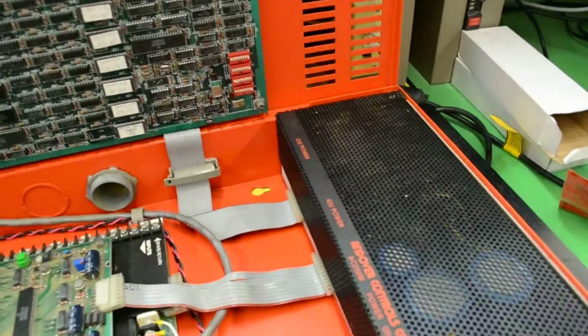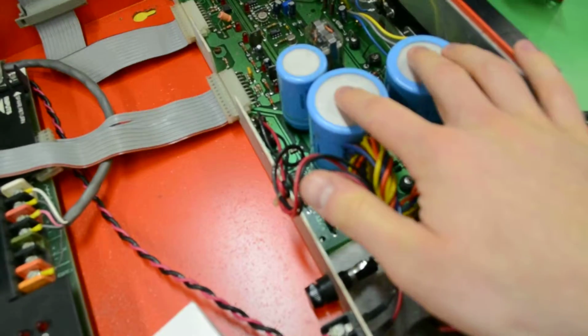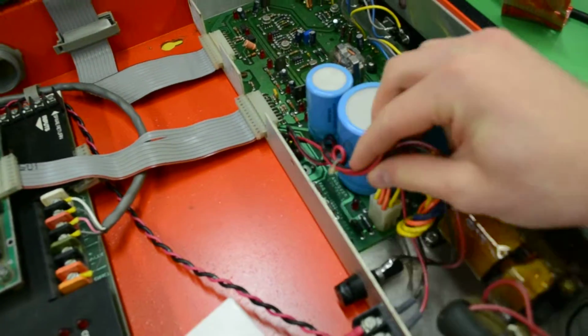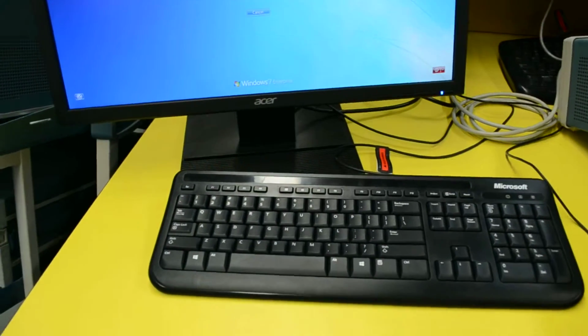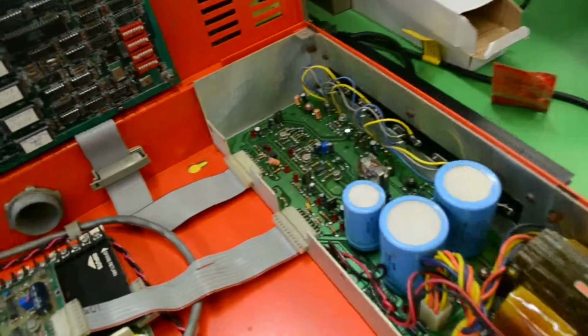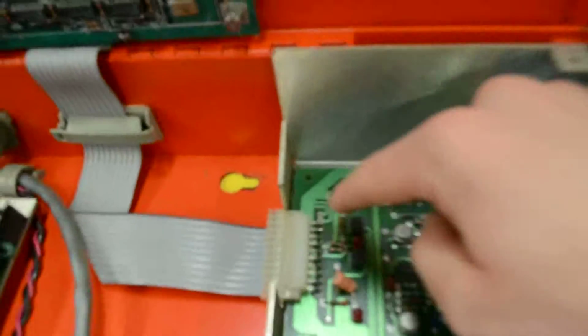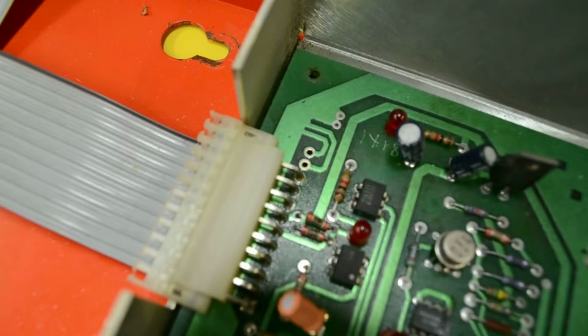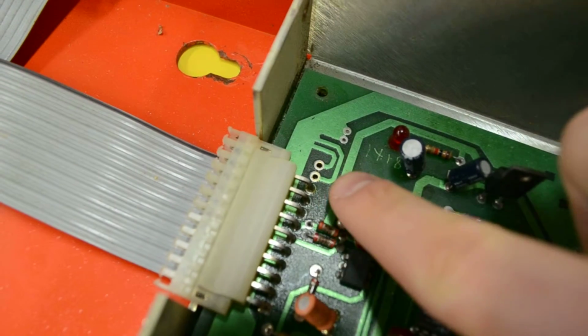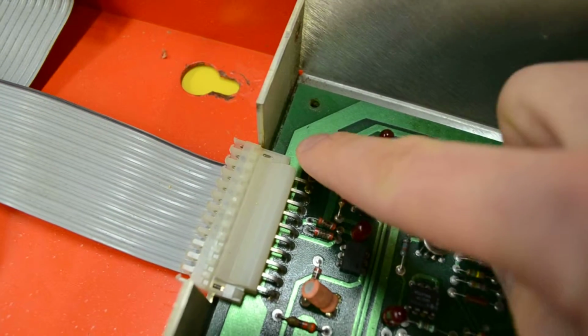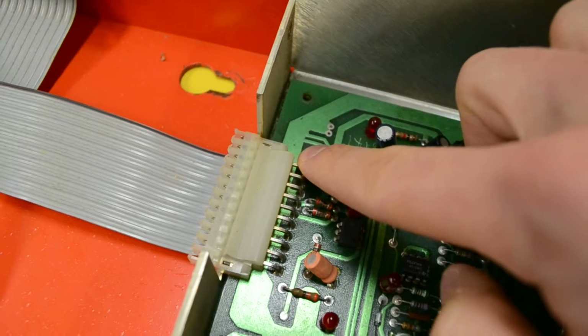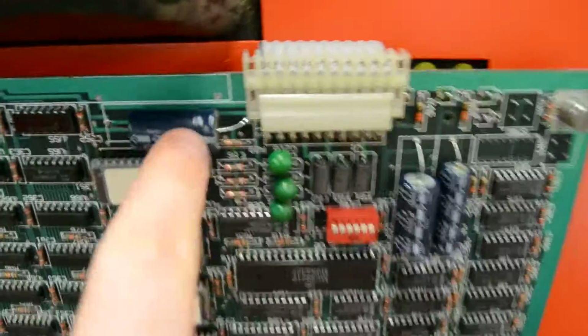We have been taking a look at the power supply. Yes, it has old electrolytic capacitors, but they're all very high quality ones, and we've hooked a scope up to it and analyzed everything. All the outputs are clean. The only thing we noticed is on this pin, right here, there's a very nasty AC/DC signal. We don't really know what it is. It's just a really nasty signal. It actually does not come from the power supply. It comes from the intelligence board. It comes from this pin right here.